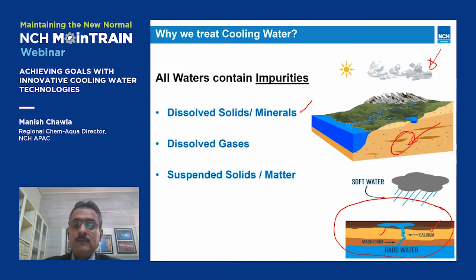Now, because we're talking about cooling systems, I have shown here, just for illustration, that cooling systems can have an open circuit and can have a closed circuit, right? So, for example, in this particular diagram, there is a cooling tower here, which is catering to the condenser of your chiller. Cooling tower water is going into the condenser, taking the heat from the hot refrigerant gas, and cooling that refrigerant gas. But in that process, it is getting hot and coming back to the cooling tower and then gets cooled in the cooling tower. So, this is the open circuit.